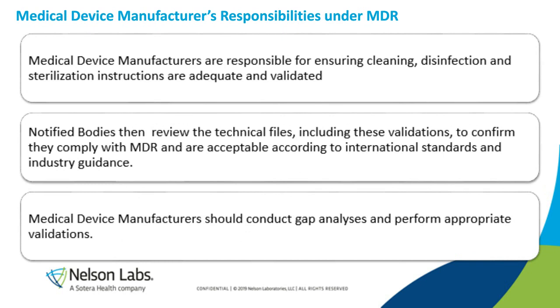Now I just want to reiterate some responsibilities for medical device manufacturers under the medical device regulation. Medical device manufacturers are responsible for ensuring cleaning, disinfection, and sterilization instructions are adequate and validated. All notified bodies will then review technical files, including the validations, to confirm that they comply with medical device regulation and are acceptable according to international standards and industry guidance. The medical device manufacturer should then conduct a gap analysis and perform appropriate validations.